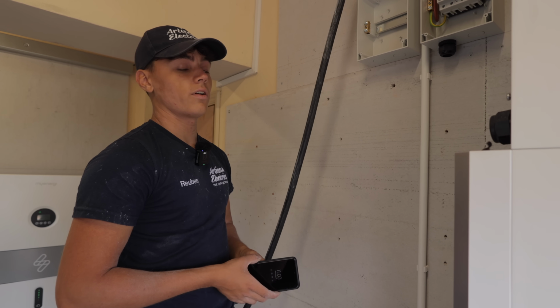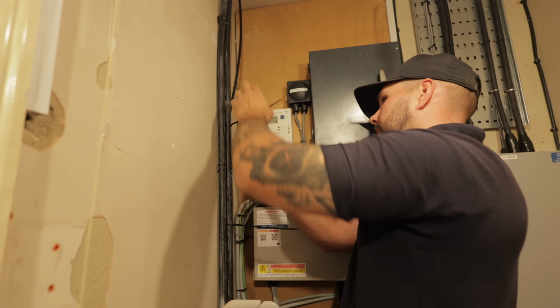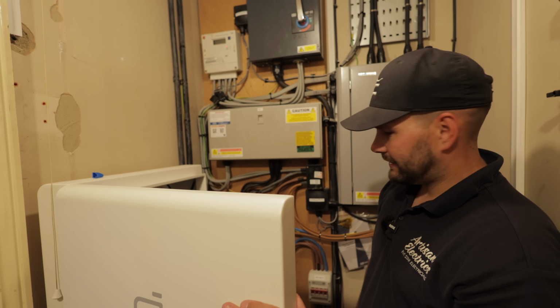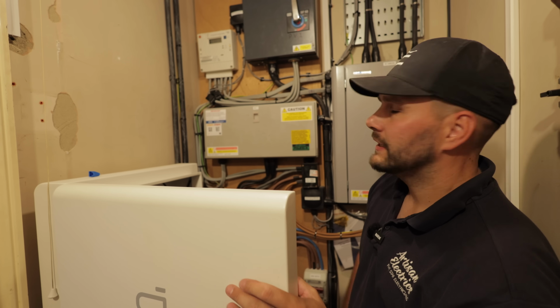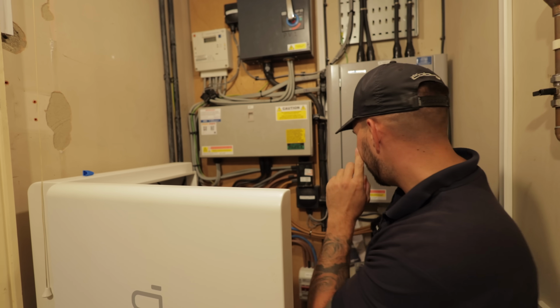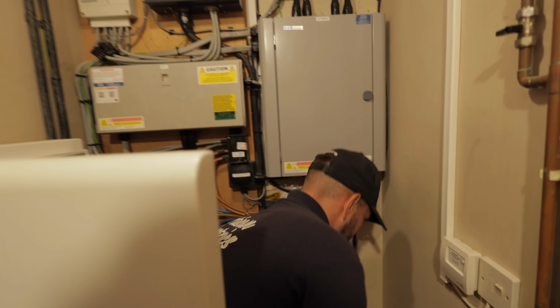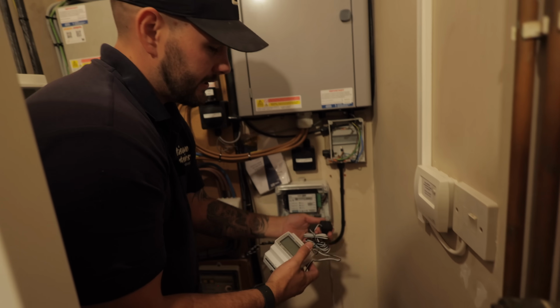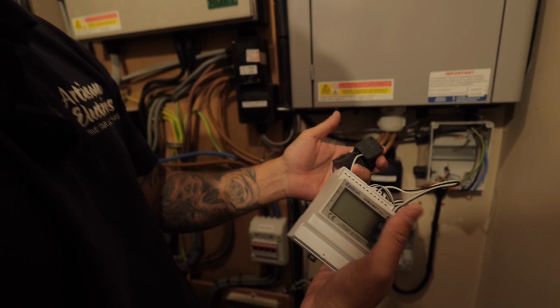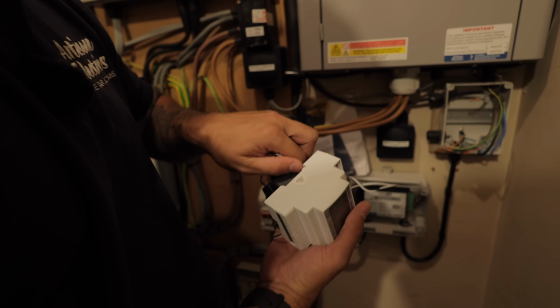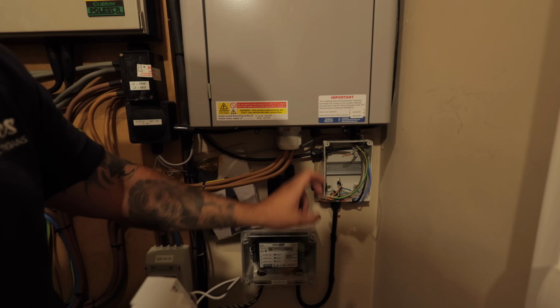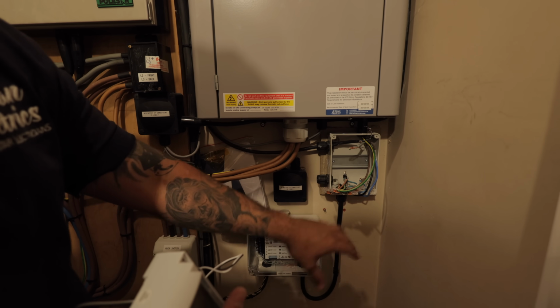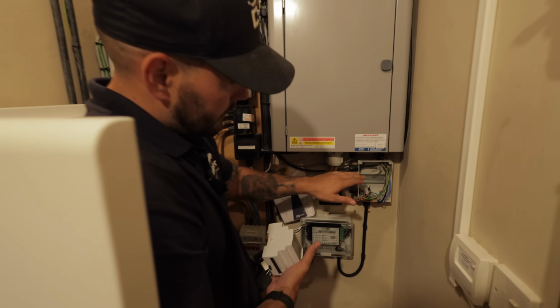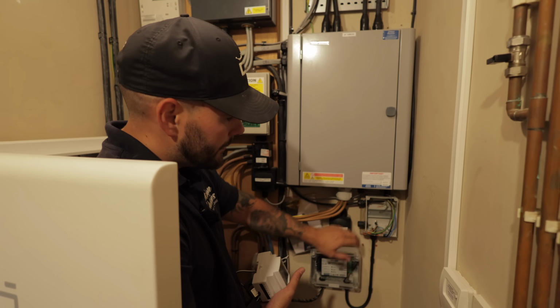Very nice day actually. I've got the cables fixed to the wall and all dressed here into this gateway. There's a couple of things left we've got to do in this cupboard. The old system here had the meter on with the CTs, 3 CTs for L1, L2 and L3. So I've got to get this meter in here. Obviously this one's a bit small, so we're going to put another enclosure below and bring some of the wiring in there, and then just put this by itself in there just so there's a bit more room.